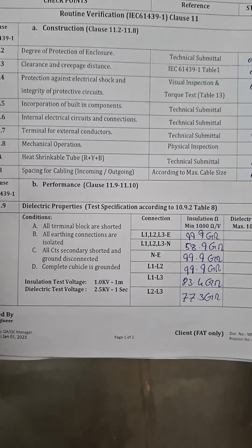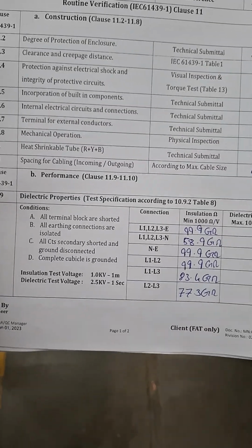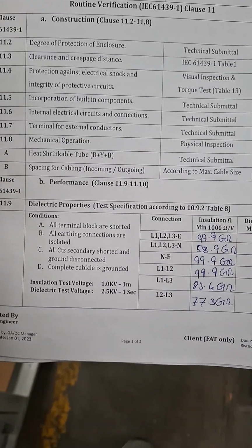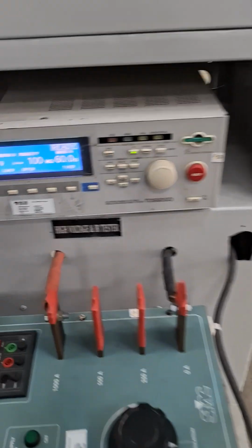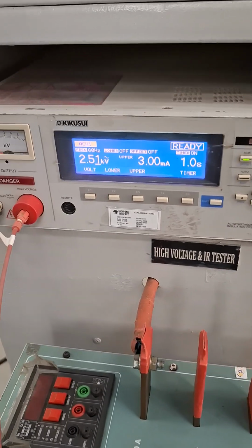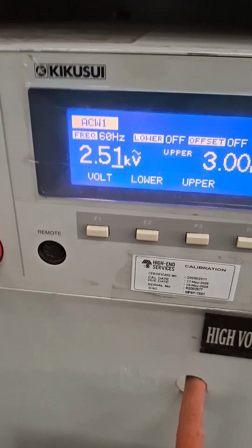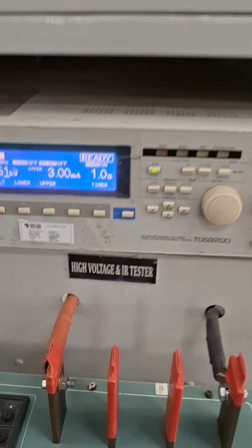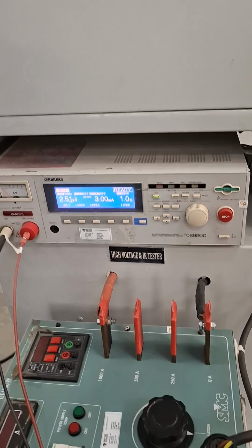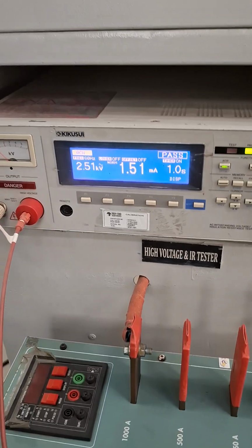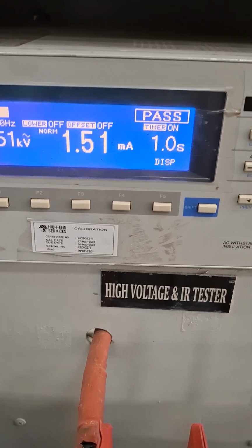Now we perform another test, that is the dielectric test, which is a high voltage test, in which we apply 2.5 kV for 1 second. Okay, first of all we apply all phases with ground. This device performs two functions. Okay, now we apply 2.5 kV for 1 second. Okay, start. Our test is passed.